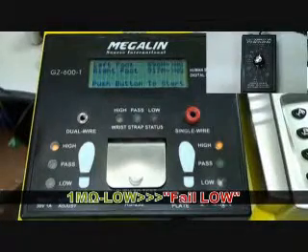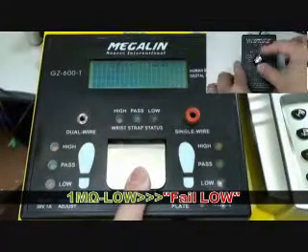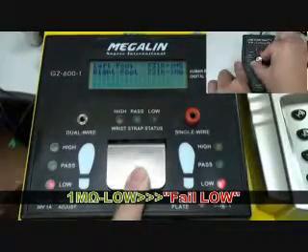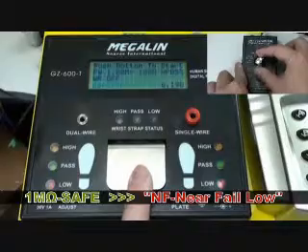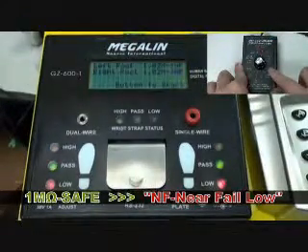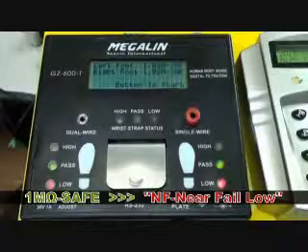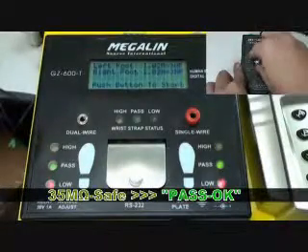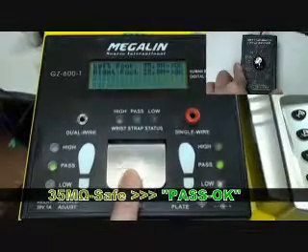We are now going to simulate the footwear testing with a dedicated calibrator. Select the 1M low range — the result should be fail low. Select the 1M safe range — the result should be near fail low. Select the 35M safe range — the result should be OK.